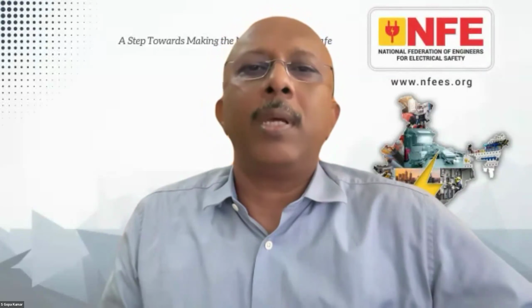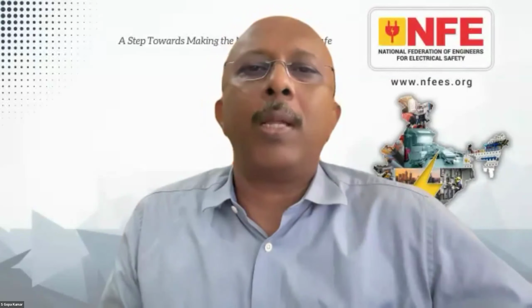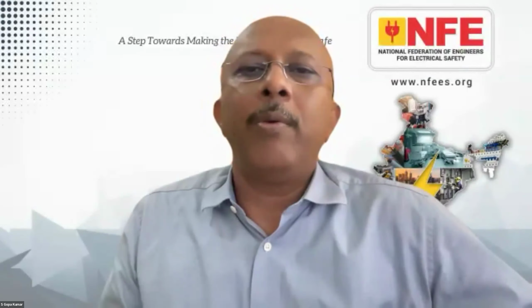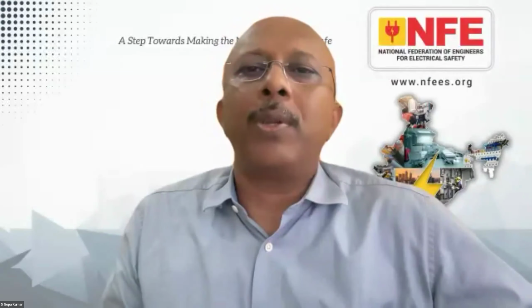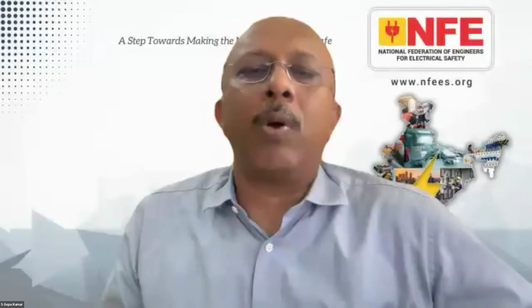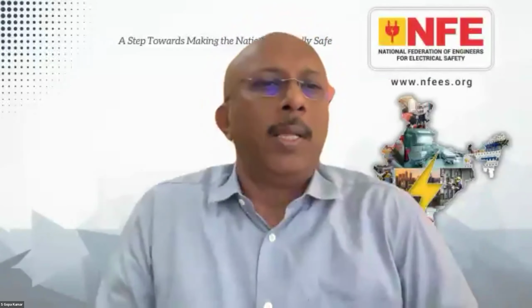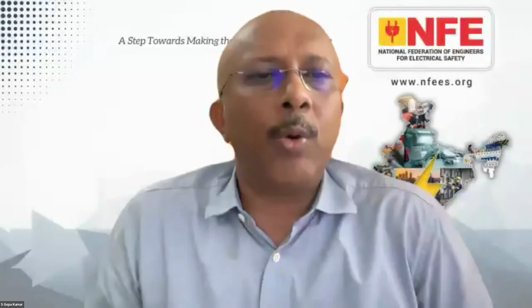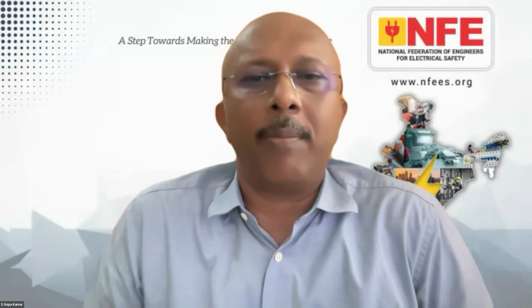The next question, again from Mr. Ravi Varma: a 4-pole RCCB has been used only for 2 poles plus neutral. One phase is not connected. What will happen? Krish, the question is, there's a 4-pole RCCB, but only 3 poles are used. What happens? So this depends on the manufacturer of the RCD. Some manufacturers of RCD, I think Gerard, you can answer this question. Yeah, you are muted.